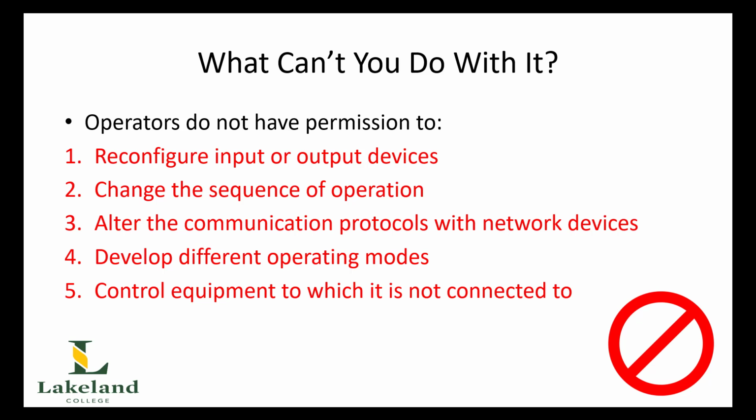We are also not able to develop different operating modes. The only modes that we have to work within are automatic mode and manual mode. Now, that also begs the question, well, what other kind of modes are there? Well, there are other modes where you can do things like step, and that is where you step through various sequences and hold them at different points. They'll do this, for example, for things like commissioning. Well, we're not allowed to do that under normal operations. So different operating modes we're not able to just access.